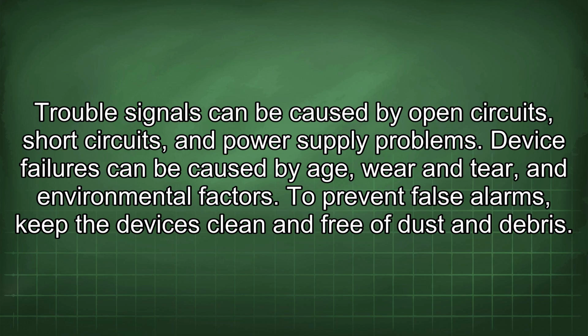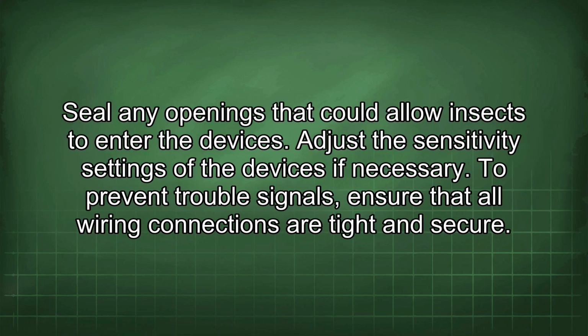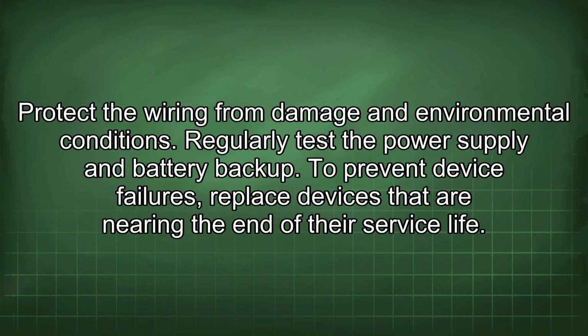To prevent false alarms, keep the devices clean and free of dust and debris. Seal any openings that could allow insects to enter the devices. Adjust the sensitivity settings of the devices if necessary. To prevent trouble signals, ensure that all wiring connections are tight and secure. Protect the wiring from damage and environmental conditions. Regularly test the power supply and battery backup.